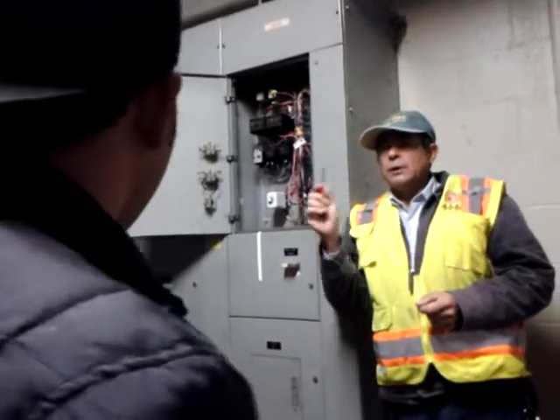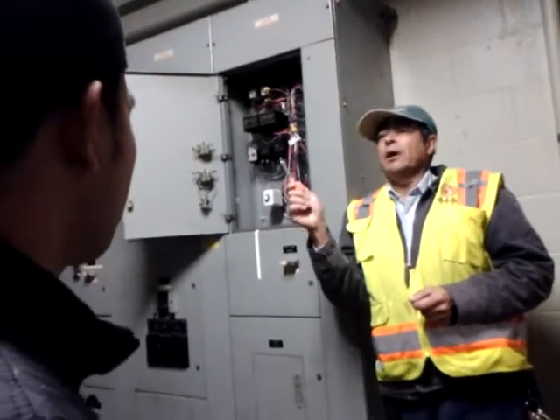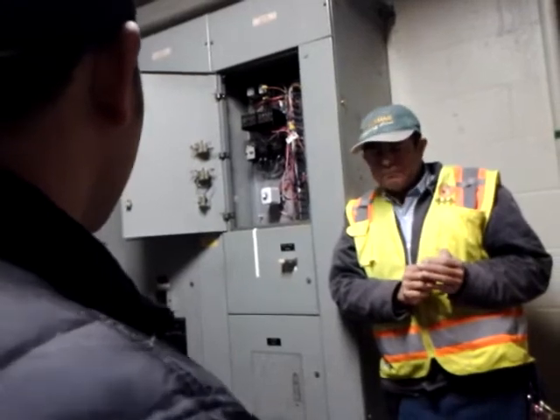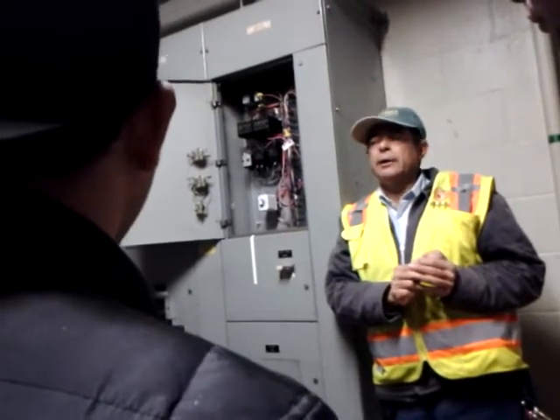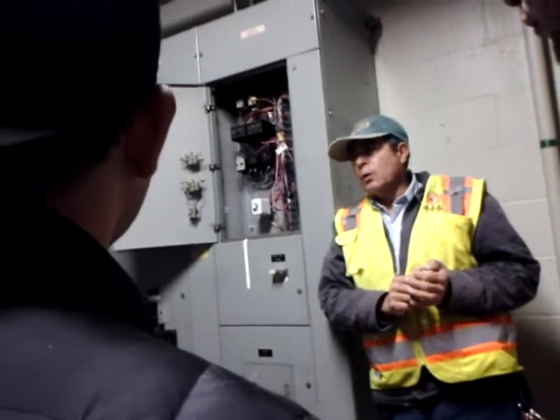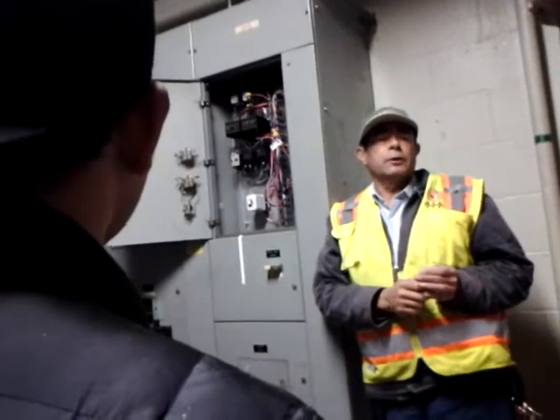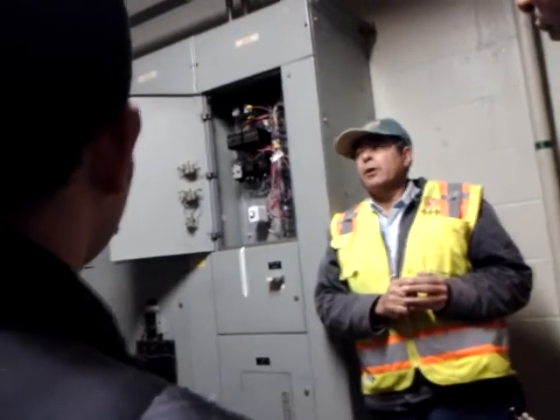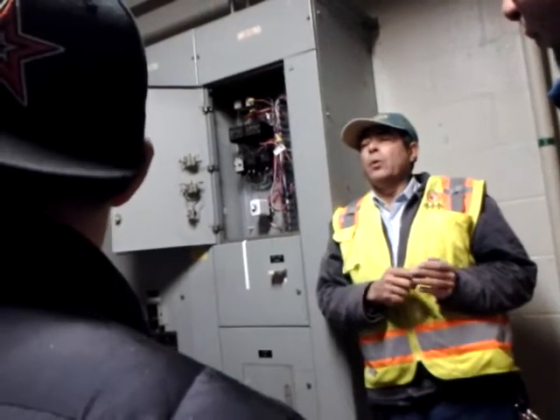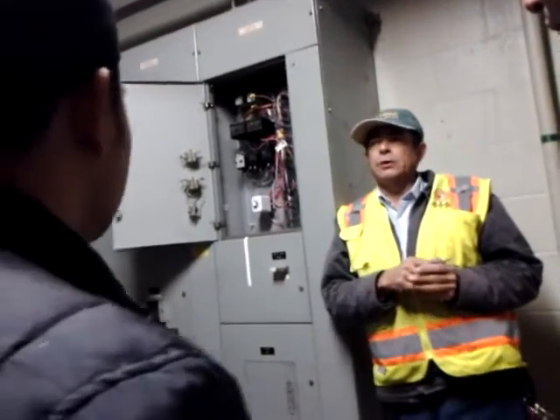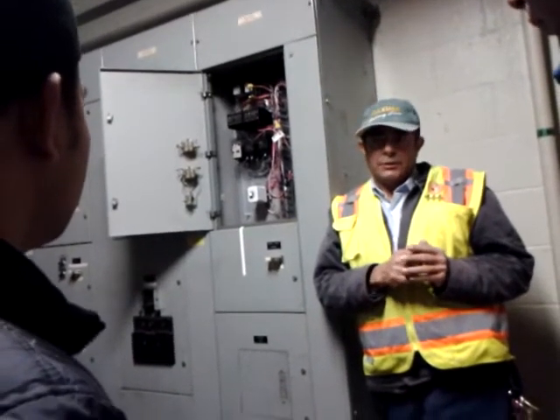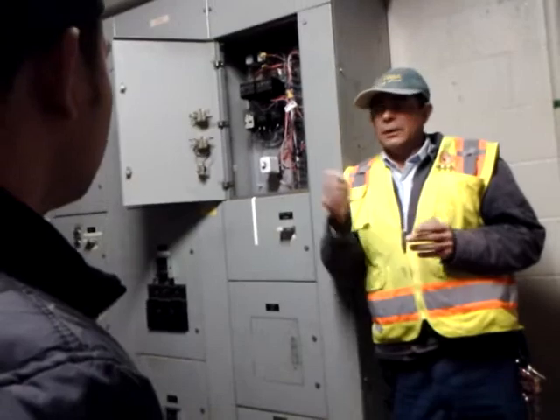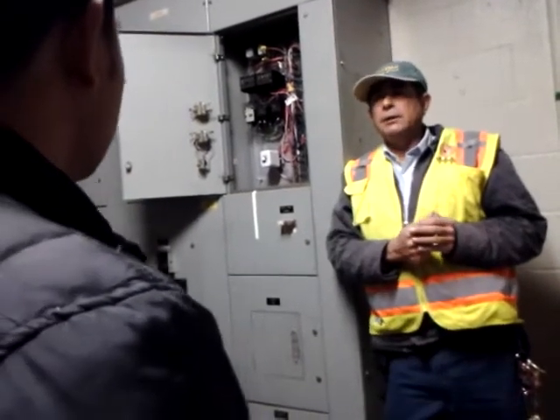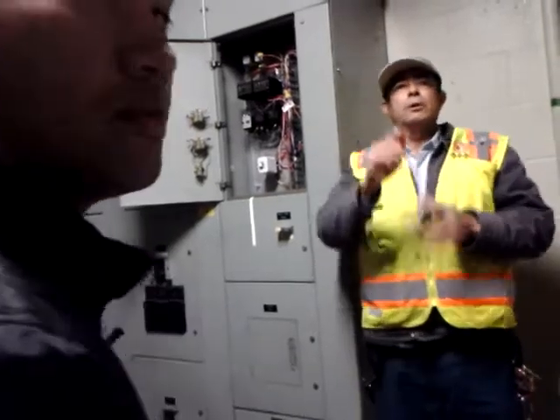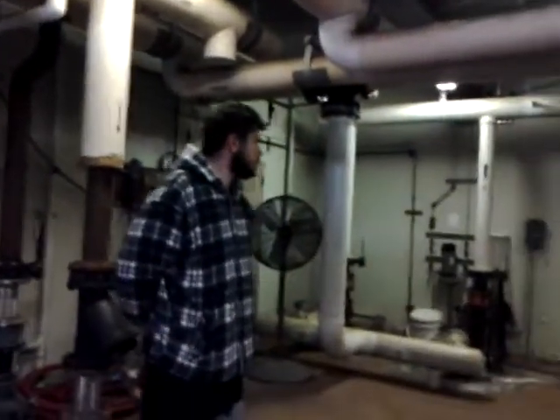And it starts with that little motor that I was telling you about, you guys will be able to hear it. And it will start injecting oil into the compressors. Once that oil sensor senses that there is oil in there, you'll hear the humming of the compressor and it will start. So once that chiller starts and it senses that the temperature of the water in the condenser barrel is getting hot, it will start the pumps. Those are the two pumps that are way out there in the corner. That is for the condenser water.